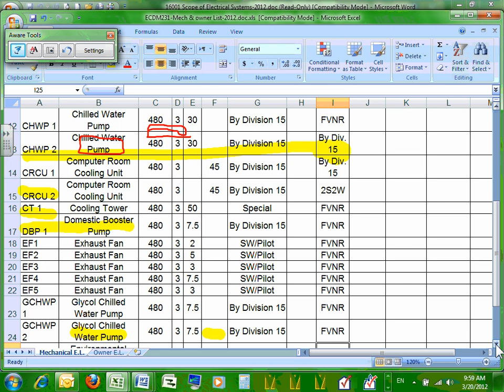I haven't asked for this, but a typical mission critical data center would have pairs of generators. So I'm redundant all the way through. Oftentimes we're redundant with utility transformers, but the Uptime Institute really says your redundancy is your 2 gen sets. That's your primary source of power for the data center. So those 2 service switchboards could go to 1 utility, and we'd still be what the industry calls a tier 4, which is the highest level of redundancy for an electrical system.